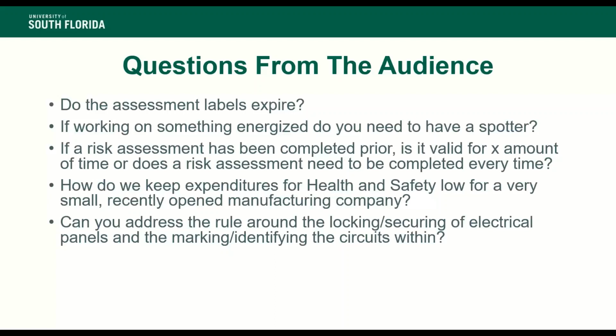However, there are a number of jurisdictions, and here in Florida, I have personal experience with one county where the local building inspector required the panels to be locked. So the employer was between a rock and a hard place. Does he upset the building inspector, or run the risk of being penalized by OSHA for locking it and making it inaccessible? This particular employer opted for an alternative. He had his electrician install a disconnect switch on the supply side of the electrical panel. So in an emergency, if he needed to turn off a breaker in that panel, he could keep the panel locked but kill power to the entire panel with a single swift action. That's how that employer beat the quandary.